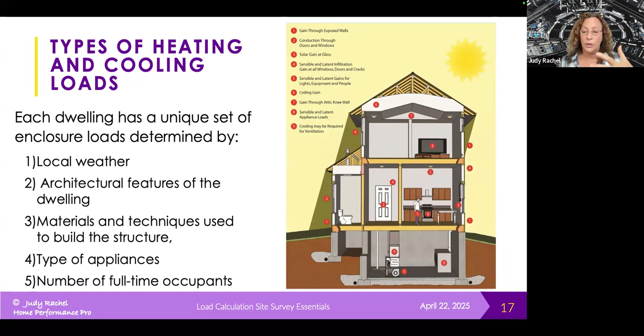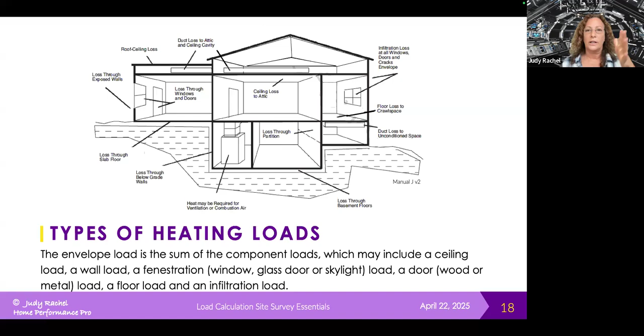So heating loads are the sum of all the component loads of the enclosure itself. That's going to include the roof, the ceiling, the walls, fenestration - your doors and windows, skylights. There's going to be a floor load, and there's going to be an infiltration load. All of those added up together are what's going to tell us the amount of energy that we need to actually add to the space for our heating load.